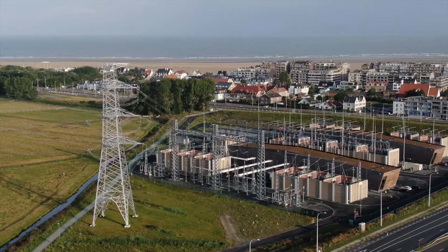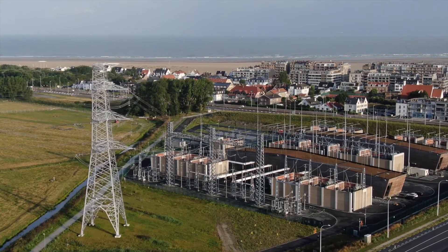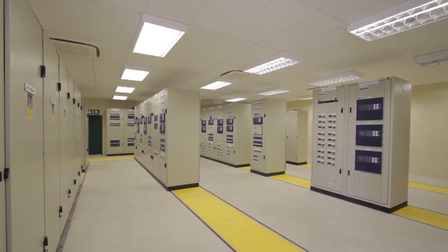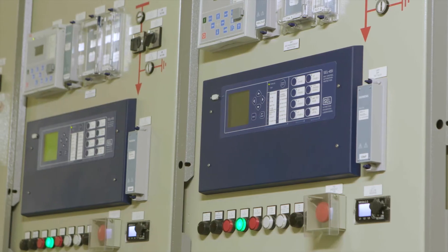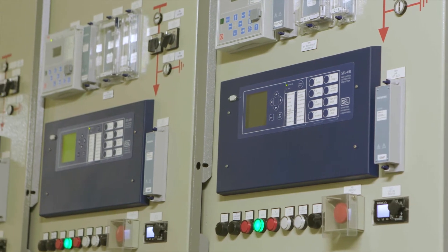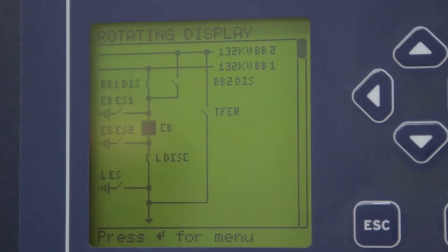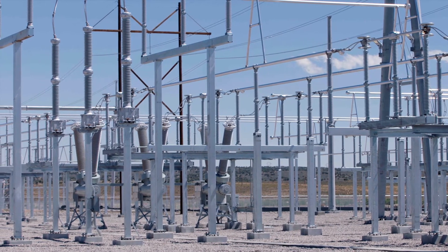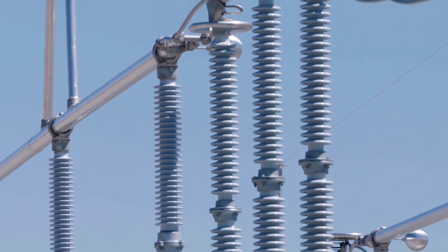The DC control power system is one of the most critical components for powering protective relay and control equipment, but in many cases the DC control power system itself is not redundant. Failure of the DC control power system can happen for a number of reasons and the results can be catastrophic — it leaves protection and control equipment without power, unable to detect faults or trip breakers.